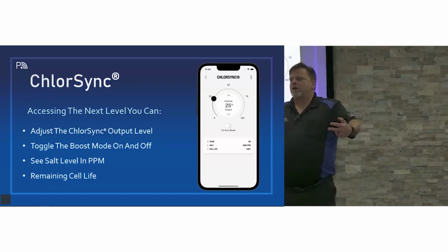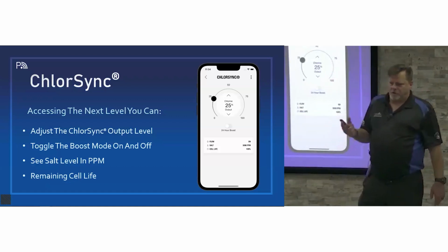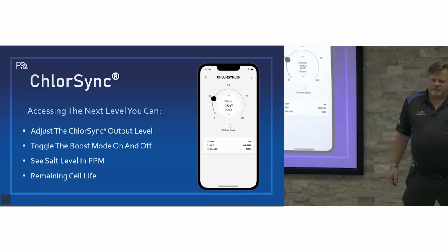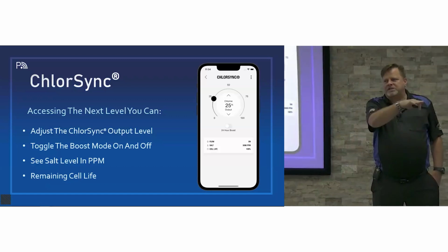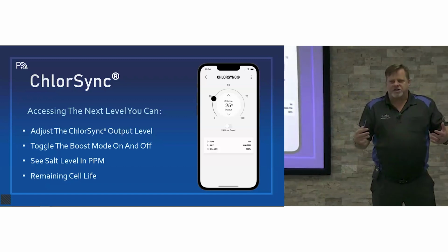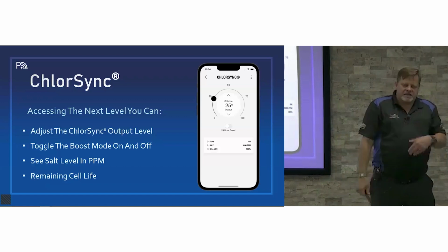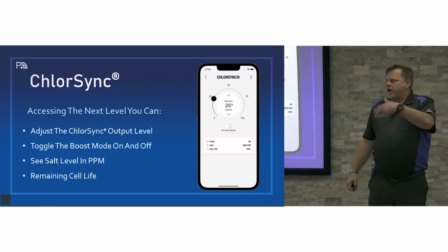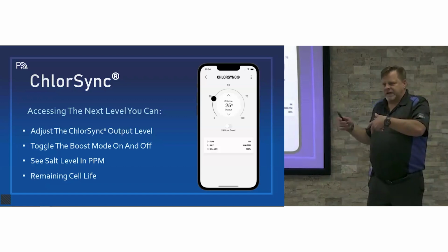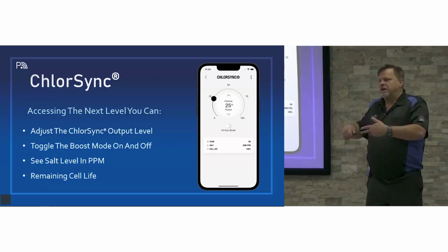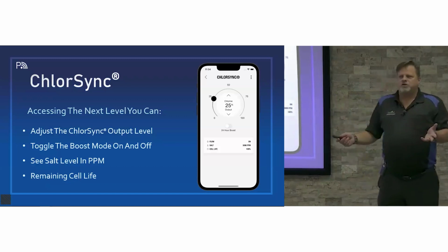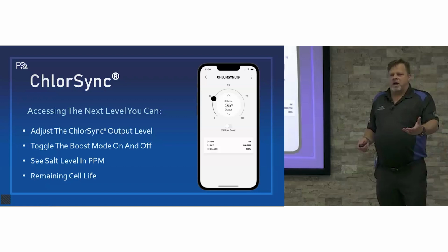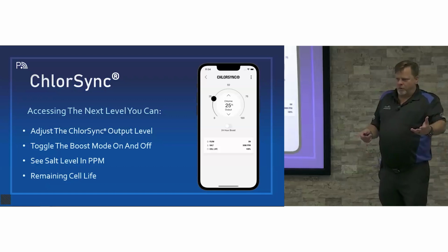One is for the pool cover and one is for the ORP control. They're specific. We were just using the pool - let's say you have the system, but you don't have complete automation, so you're not controlling groups or anything else. Sean's workaround is using the pool cover control as a way: when it goes into spa mode, it'll sense that the pool cover is closing and trick it into going to 5% of whatever the original set point was.